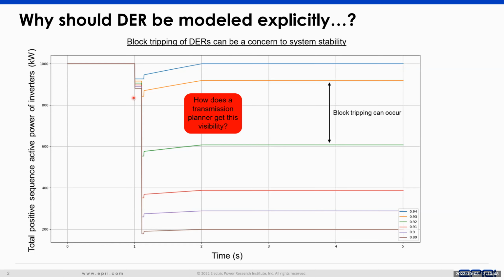If DER of such large amounts start tripping, they can trip in a block fashion, where very small changes in voltage level can cause very large changes in the amount of DER that trip. If that starts occurring, it can cause a very large disturbance on the transmission side. We need visibility so that if an unplanned event occurs on the transmission network and this kind of block tripping happens, we can see it occurring and plan for it.